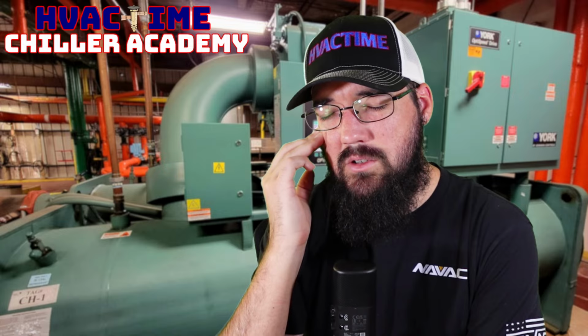Carrier 30XB, 600 ton. It's giving error under volt 1. Cannot be cleared. This error occurred after boards A and B were swapped. So that's going to be an addressing issue. Carrier does addressing on their modules, and this is just me pulling off of memory without actually looking it up in the book. That should be an address problem. When you see that, it's reading the wrong address for the module, which probably needs to be readdressed for whatever you're troubleshooting. So if you're trying to do a board swap as part of your troubleshooting process, look at the little dip switches. That's usually where they'll control the addressing on the module, and you'll need to set the address correctly on that module to then swap it between the two. I'm pretty confident that's what you're seeing there, without some extra feedback.